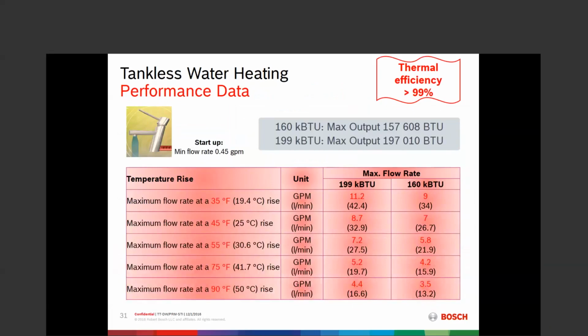Some performance stuff here, so we can talk about pretty much the worst case in North America that we would need to get to 120 degrees, and 120 degrees is a fairly common setting for a tankless water heater. These do come from the factory locked at 120 degrees. The contractor in the field with a passcode can unlock that and take the temperature up to a maximum of 140 degrees. So we're talking about a 75-degree temperature rise. That's telling us that we have water coming in at 45 degrees and leaving the unit, the set point is at 120. And we see that we can get 5.25 gallons per minute out of the 199,000 BTU unit, 4.25 out of the 160,000 BTU unit.